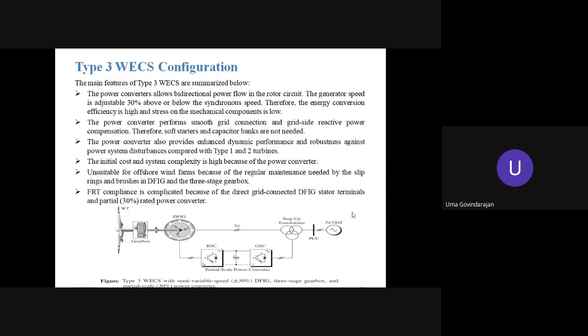During subsynchronous operation, when the wind speed is less than the synchronous speed of the machine, the generated power is available on the stator. A small amount of slip power will be supplied into the rotor, so that you can have the generation. During supersynchronous operation, the rotor power is available, and that also we can extract and give to the grid. During subsynchronous operation, the negative slip power we can supply using the same bidirectional rotor side converter and grid side converter. So you can inject into the rotor for a reliable operation for power generation. Here the FRT compliance is complicated because of the direct grid connected DFIG stator terminals and the partial use of the partial rated converters.